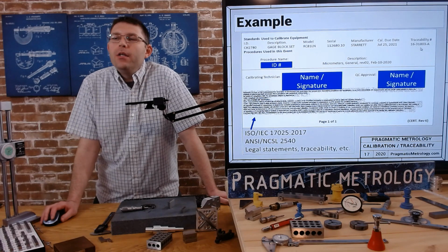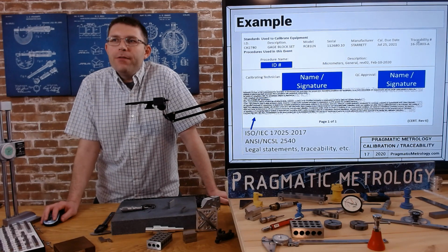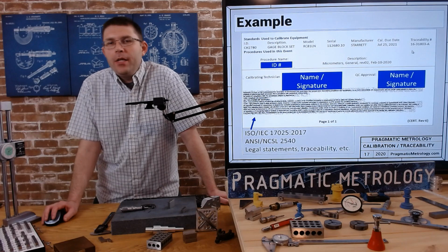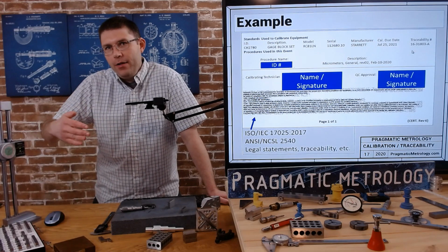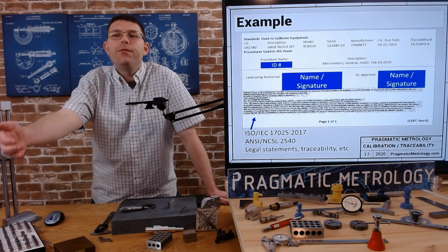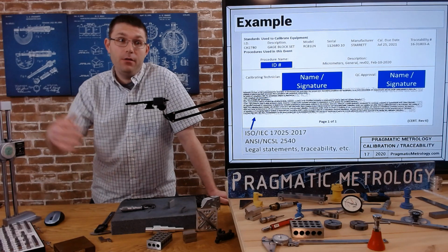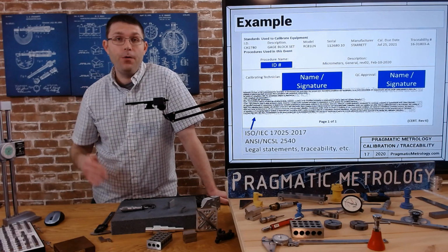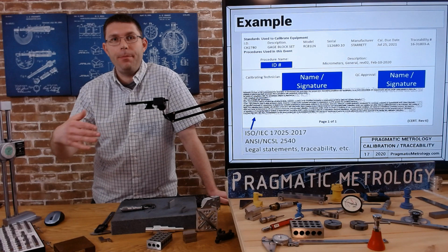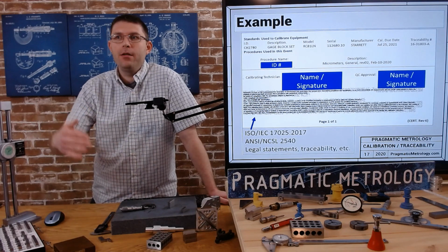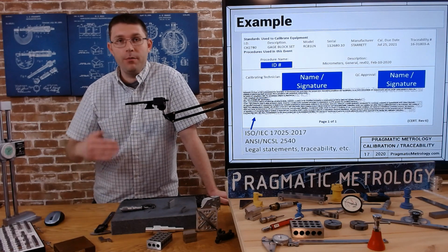So if you need to pull the information on this calibration, you can contact the vendor and ask them, can you get me the information relative to this number? And they will trace it back, and you can keep going if you need to. Some companies need to do this before they award contracts, before they accept product. They'll go through the method of tracing back the gauges. So it's really important to maintain it.